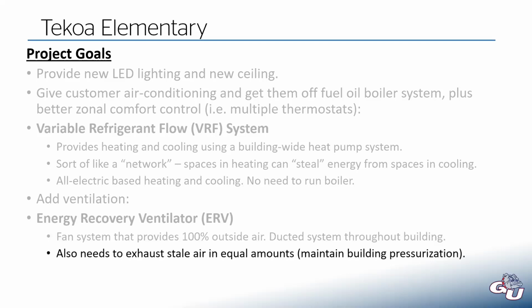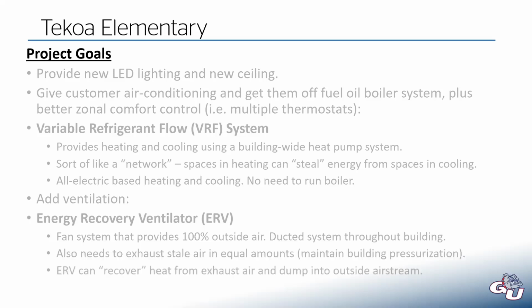The ERV also has to exhaust the stale air in the building in an equal amount because we can't pump in fresh outside air without getting rid of the old stale air. Otherwise, what will happen is you're going to start to pressurize your building, and eventually it will get to the point where your doors start blowing open. The other key part to an ERV, the energy recovery portion of its name, is that it can recover heat from the exhaust air that we're getting rid of and use that to preheat the outside air. And that will make more sense here in a moment. And ultimately, a goal is we want to save them energy.